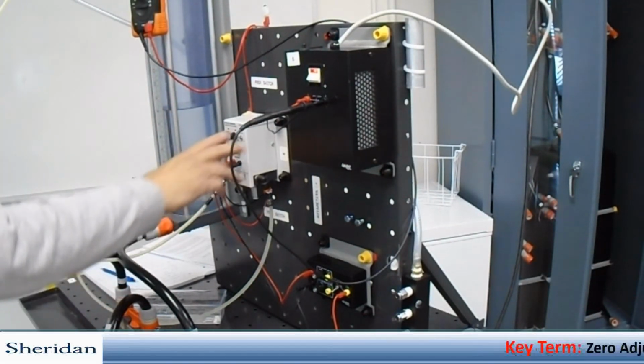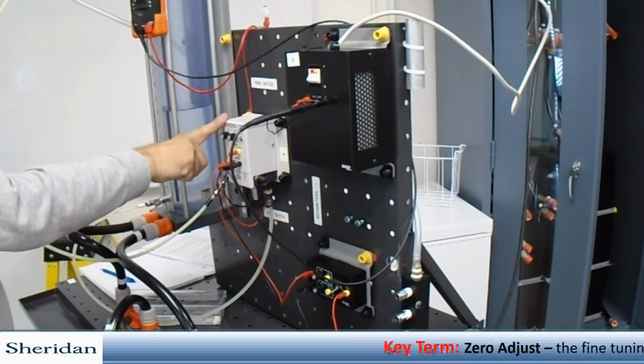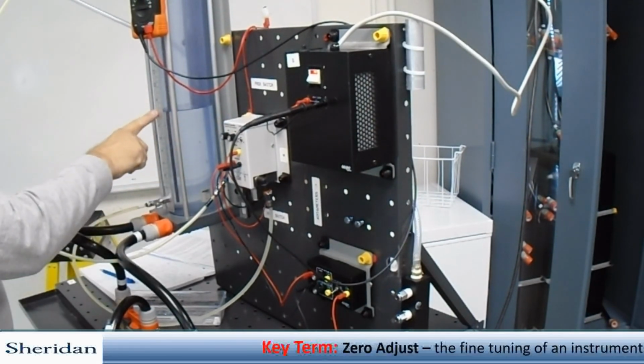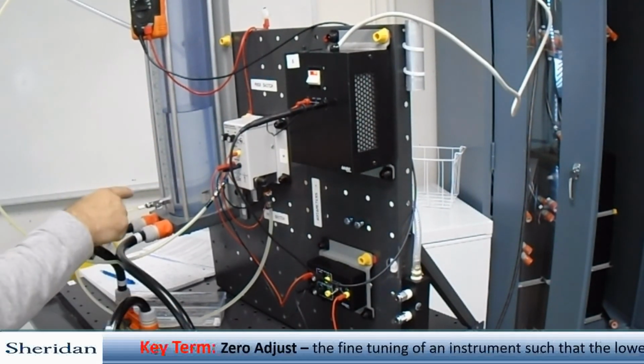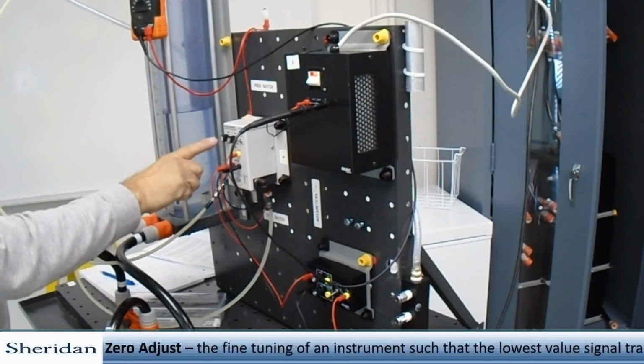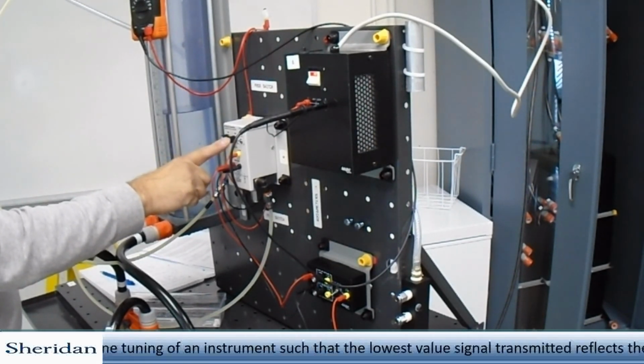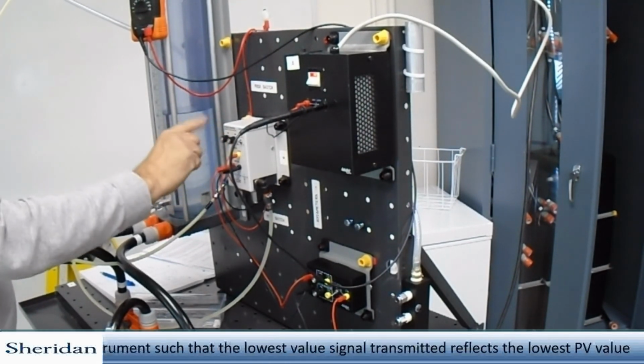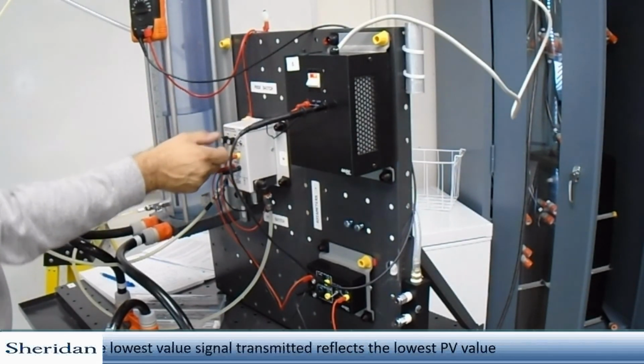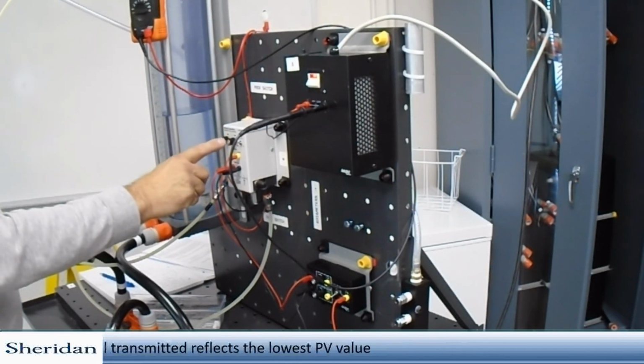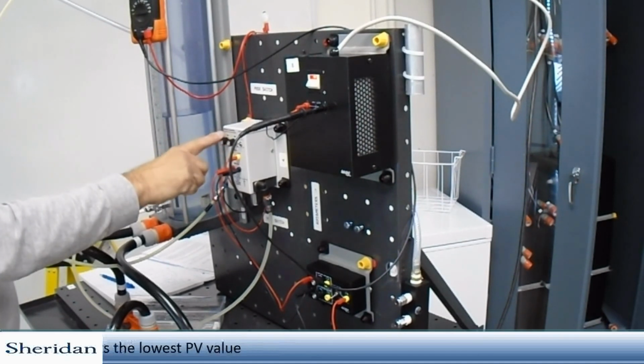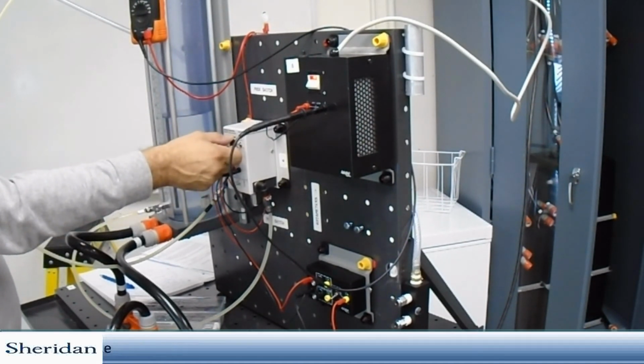The next part, we're going to start calibrating our pressure transmitter. And to do that, we're going to set the water down to a lower level. The first thing we have to do is set our zero and our span switch to maximum. So we're going to turn that clockwise, both of them, and in each case they should take about 14 half turns to get it to go to completely maximum until you hit the stop.